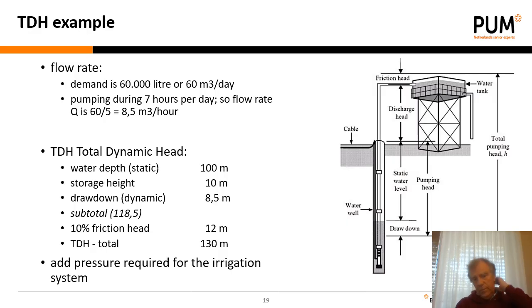Say the total dynamic head, say the water depth is 100 meters, say the storage height is 10 meters, the dynamic drawdown is 8.5 meters, and that's a subtotal of 118.5. Say we have a 10% friction head, then we need 12 meters extra, so the total dynamic head will become 130 meters. Remember that we said in the last sheet that we need 10% extra.